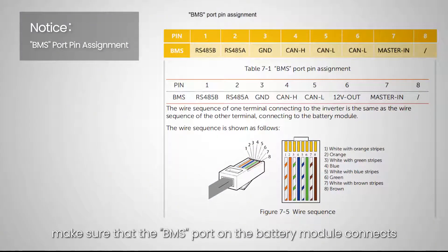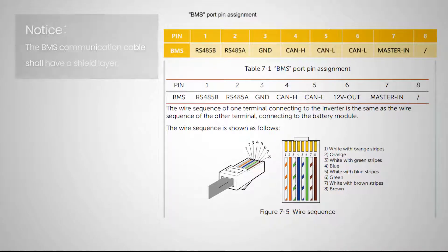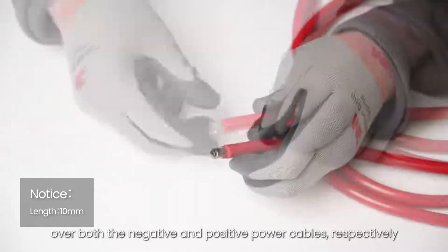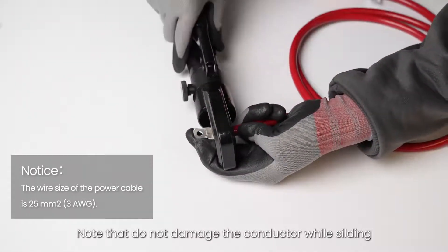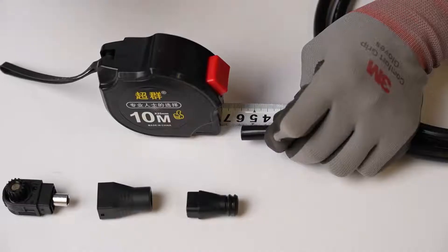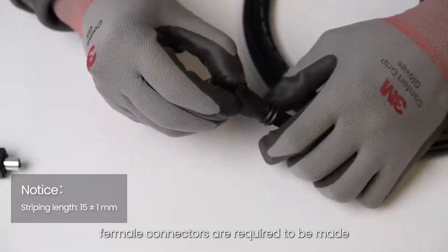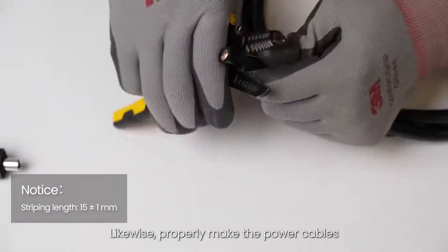For communication connection, make sure that the BMS port on the battery module that connects to the inverter is pin to pin, and the cable shall have a shield layer. Before connecting to the inverter, ring terminals are required to be made and fitted over both the negative and positive power cables respectively. Note that do not damage the conductor while sliding the jacket off the power cable end. In the event that two or more battery modules are purchased, female connectors are required to be made. Likewise, properly make the power cables.